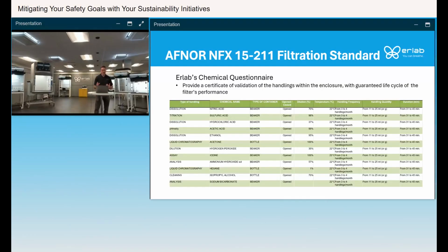a filtration efficiency. And for that, with all that testing we've done, we have each customer fill out what we call our chemical questionnaire. This is going to list the chemicals they're using, the types of containers they're in, the temperature they're used at, because that all affects the evaporation rate of the chemicals, the quantity per month, how often they're using it. From all that testing we've done in our test chamber with the carbon filters, we then take the information on this chemical questionnaire, plug it into our algorithm, and then we're able to give you a filter lifetime in months before 1% of the threshold limit value of all those chemicals you're using would be detected past the exhaust of the carbon filters.